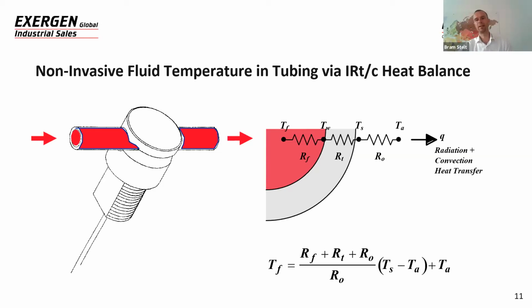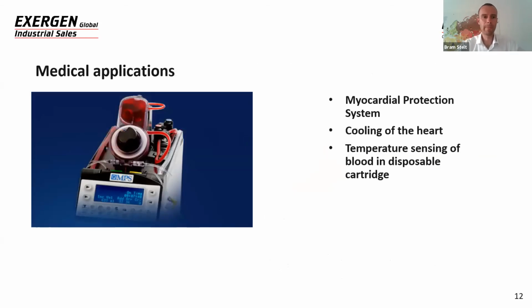Yeah, thanks, Bob. And I'll get into some examples now. Maybe it's good to add that what you see here on the left side is one of our IRTC models that has been screwed into a clip, and the clip is especially designed to hold a medical grade tubing, so that the tubing is exactly positioned in the field of view of the sensor. I'll explain a few medical applications right now of this heat balance.